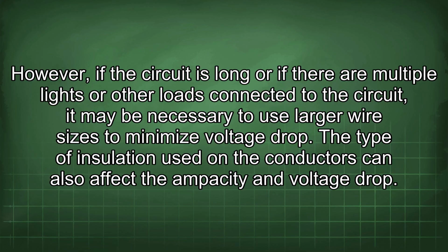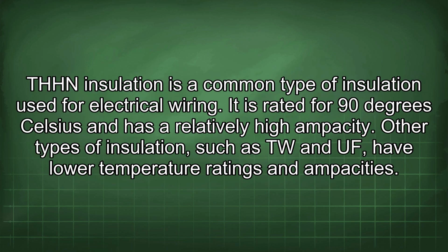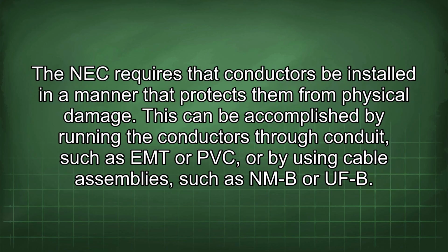The type of insulation used on the conductors can also affect the ampacity and voltage drop. THHN insulation is a common type of insulation used for electrical wiring. It is rated for 90 degrees Celsius and has a relatively high ampacity. Other types of insulation, such as TW and UF, have lower temperature ratings and ampacities. The NEC requires that conductors be installed in a manner that protects them from physical damage. This can be accomplished by running the conductors through conduit, such as EMT or PVC, or by using cable assemblies, such as NMB or UFB.